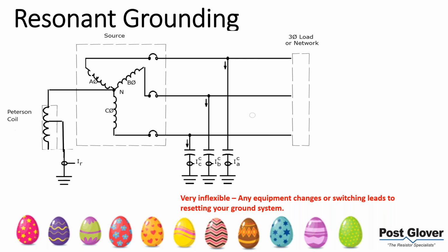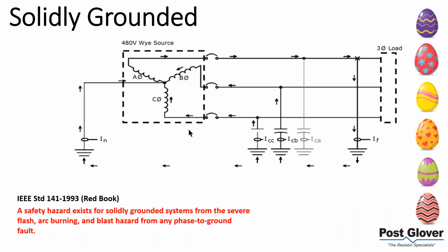If you're doing switching or modifying your system, you're going to have to retune the coil, and this becomes impractical for most applications. Now, if this fits for you, by all means, it is an interesting application, but it's very limited in what you can do with it. Of course, you move on to solid ground systems. Generally speaking, industry-wide, especially in commercial, you see solid grounded.